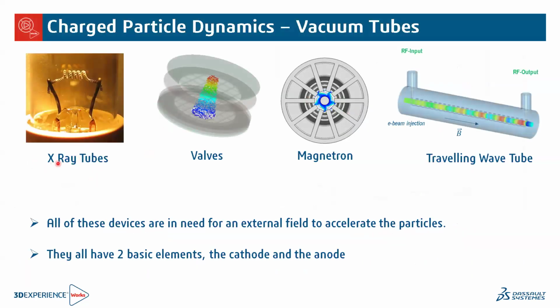Now, we do have other applications. For example, we have X-ray tubes. We have a lot of users that use our tool to design their X-ray imaging machines. How an X-ray tube works: you see here we have a tungsten filament. When you inject a high current, you are heating up this filament and releasing electrons. So the electrons are released from the filament under the effect of the temperature. Those electrons are accelerated again by a field. Finally, they hit a target that is probably made of tungsten. When they hit this target, they lose energy. Some energy will be absorbed and translated into light, or into a photon, or into an X-ray. And this is how you create X-rays.